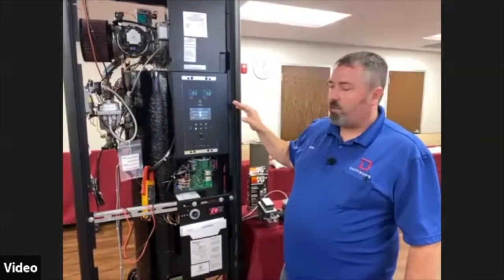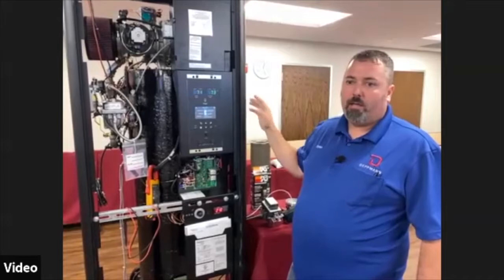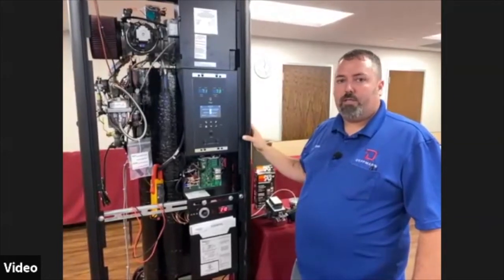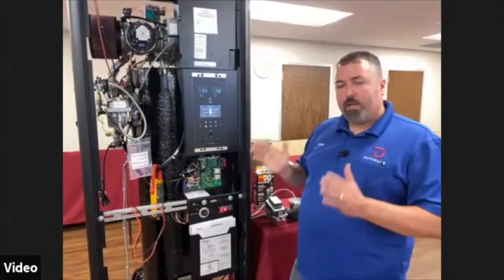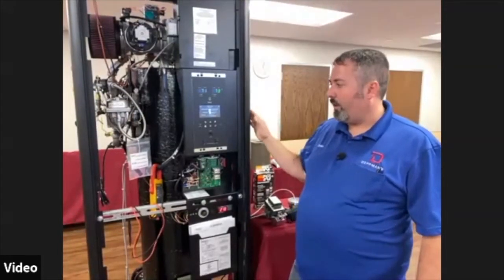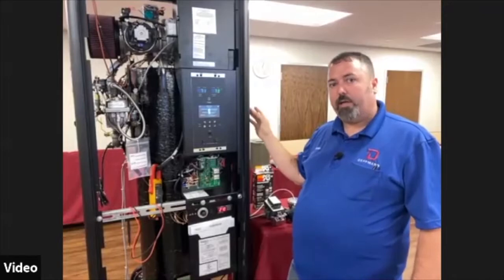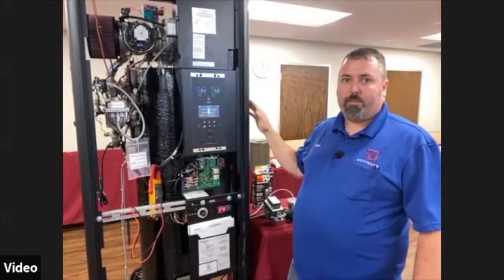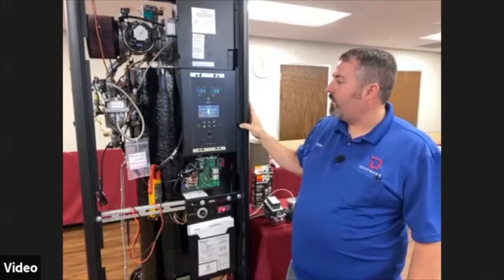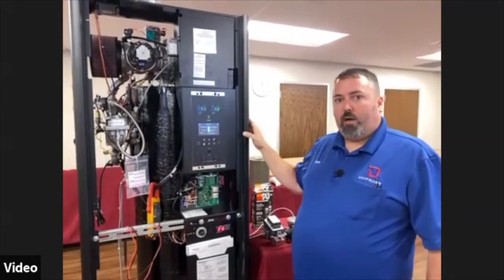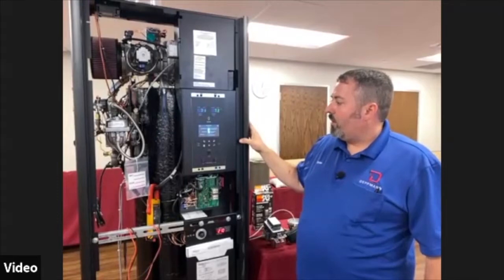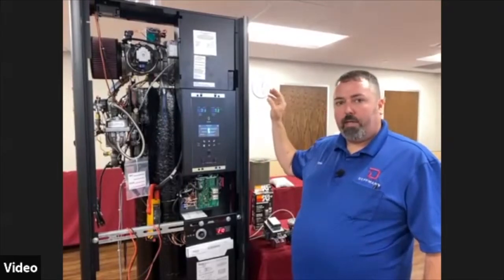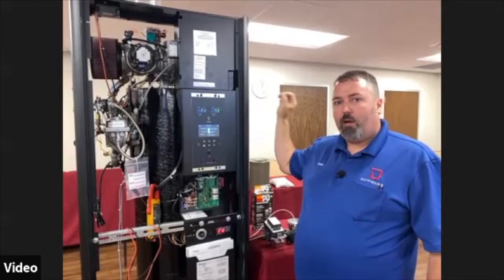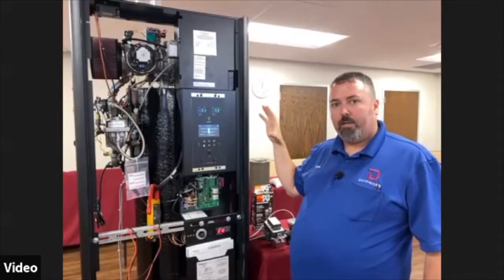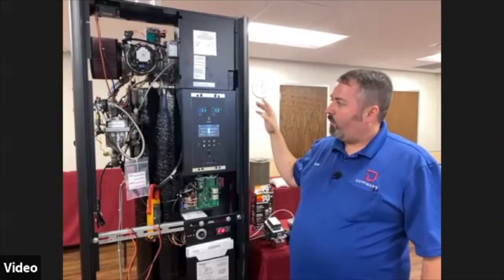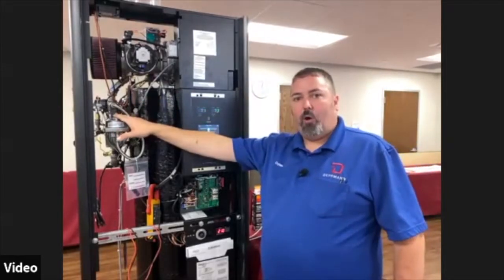And the second function, Ron showed you the current sensing relay on the backside. We're sensing the current through the ignition transformer so that if it's not between a certain window, which is 0.1 amps and 0.4 amps, it knows there's an issue with either the igniter or the ignition control. So it'll stop the firing sequence then so that we don't have a hard light off. Once we've proved our amp draw across our ignition transformer, it will then open the voltage to the pilot solenoid and allow the pilot solenoid to allow gas through and light the pilot. And after a 2-second delay, it will send power to the SSOV and open main flame.